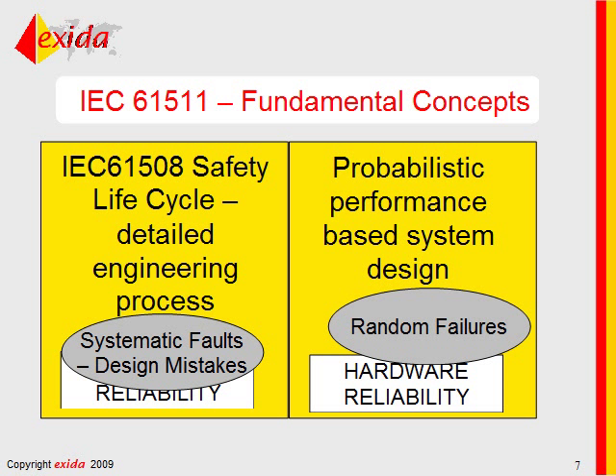The other fundamental concept in 61511 is that designs are performance-based. Performance-based. What do you think that means? The intent here is that there are no rules. It's not what we call prescriptive. There's nothing in the standard that says that for an overpressure safety function you must use 3 transmitters, and you must vote them 2 out of 3, and you must have 3 valves, and double block and bleed, and you must use a TMR logic solver. No, no, no. There's none of that.